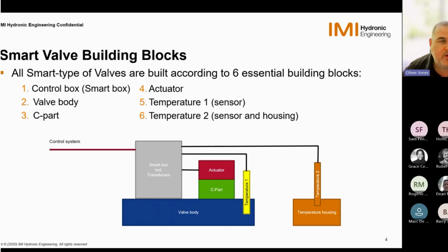So if we take a look at the essential building blocks of how the TA Smart or a smart valve is put together, typically we have a control box, which is our smart box that sits on the back of the valve. The valve body itself, obviously to house all of the components. Our C part, which is our plug and seat mechanism. This is what is actually controlling on the valve, and the actuator above it, which is driving that control. Then our temperature sensor, which is mounted internally and connected to the smart box, and our second temperature sensor and the housing, which is mounted on the opposite side of the valve and is also fed back to the smart box. And these internally come back to the control system, so they are fed and output back to the BMS effectively.